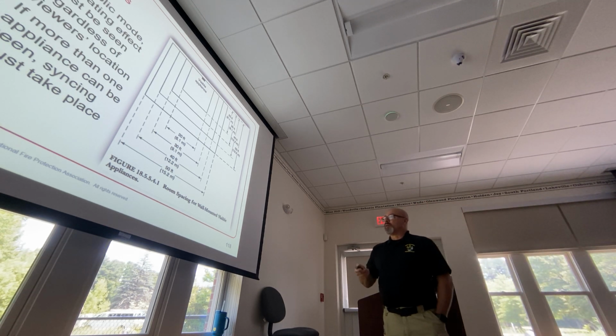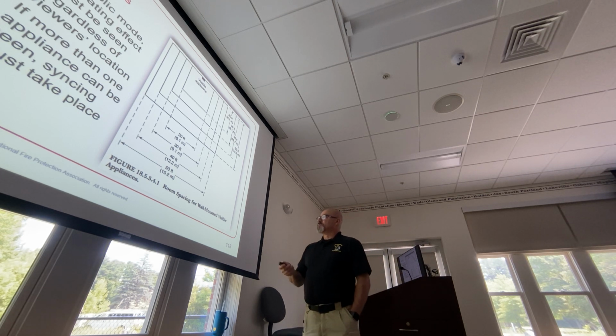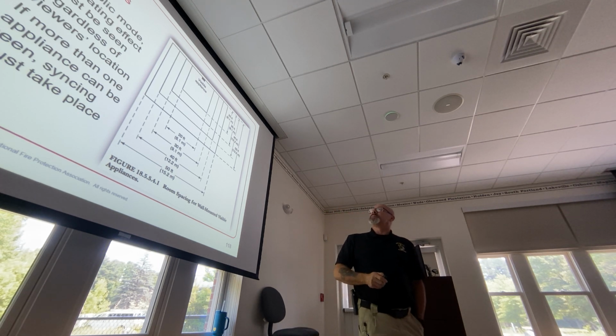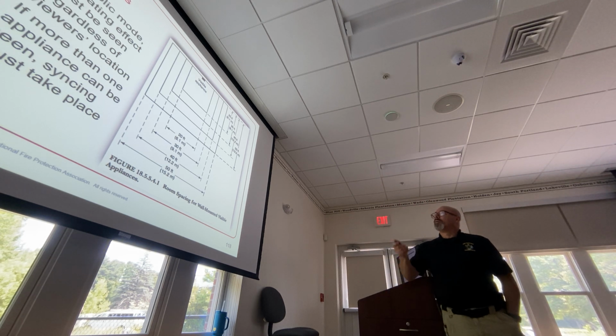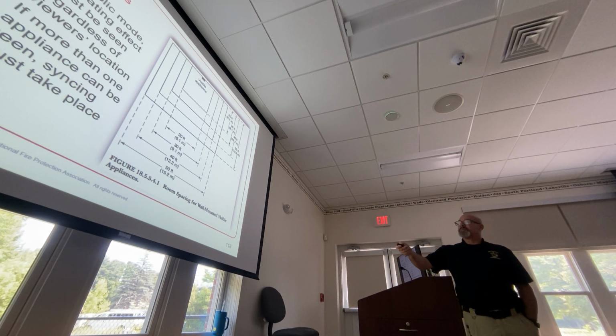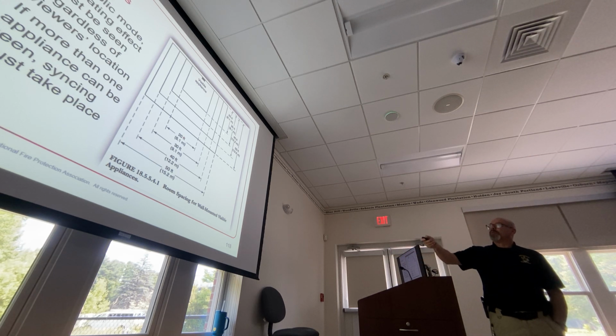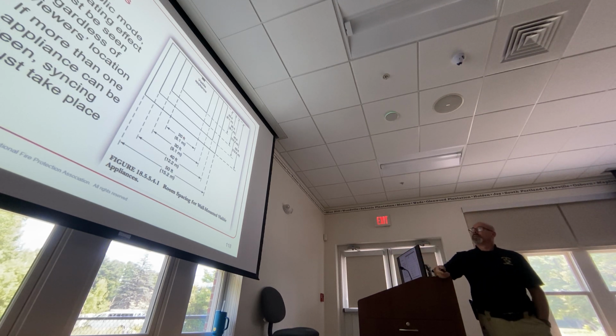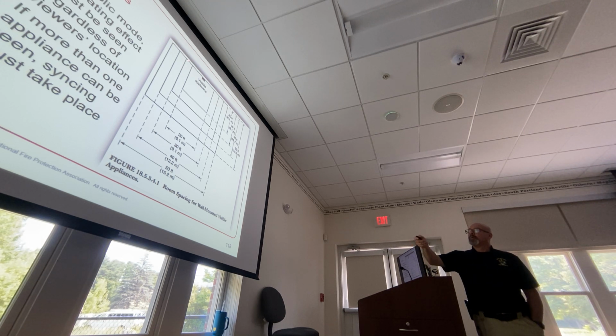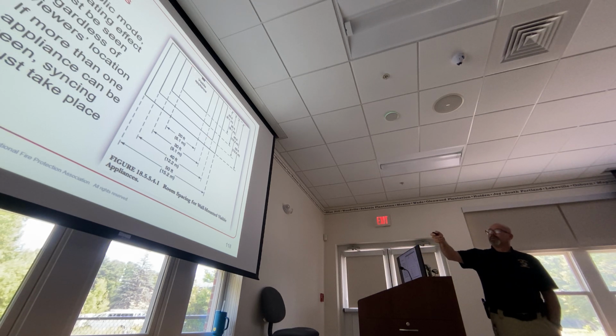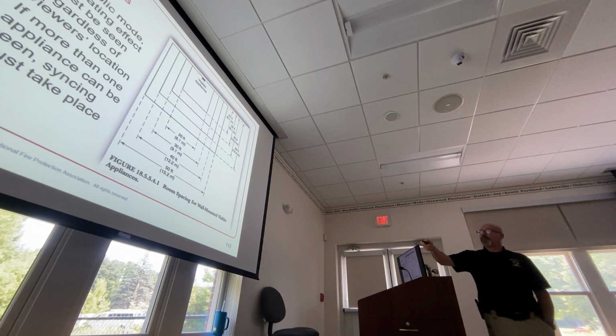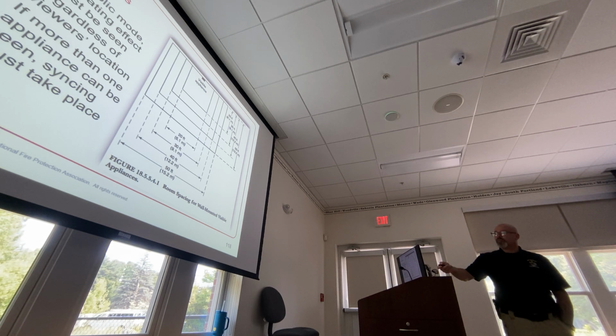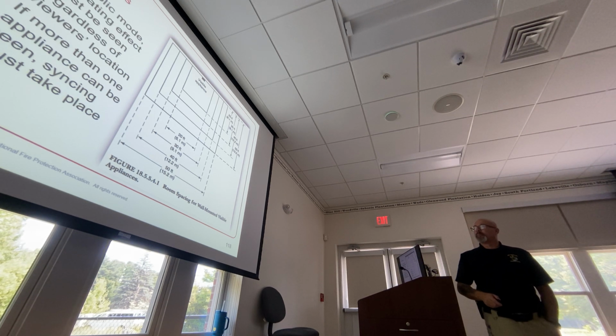So, Figure 18.5.5.4.1, room spacing for wall-mounted visual appliances. All this is just giving you your room spacing, 20 feet by 20 feet. That is your square box, okay? As you grow bigger in your box, you start off with your 20 by 20 box here. That's what these mean. Then you go to your 30 by 30 box, your 40 by 40 box, your 50 by 50 box. That's giving you your room spacing for wall-mounted visible appliances.